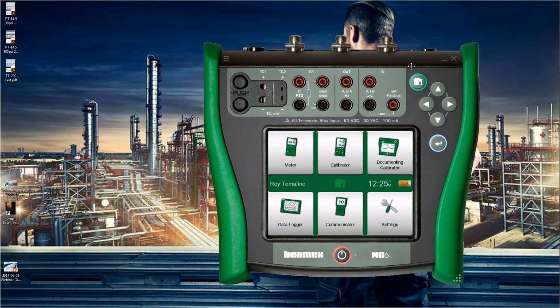The calibration lab. Here's what I have. I've got a calibrator, and it's got a bunch of different connections hooked up to it. This is what I'm going to do. The first example, I have a pressure transmitter, and I've got a pressure source, and I have a pressure hose that has three different legs on it, and it's going from the calibrator to the device under test and then to our pressure source.